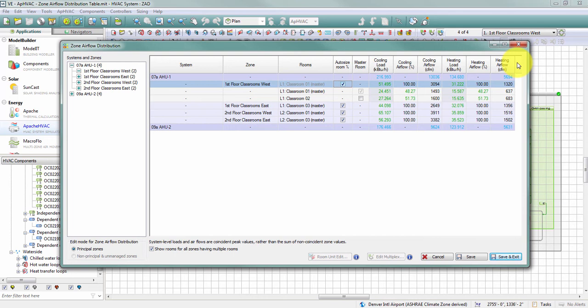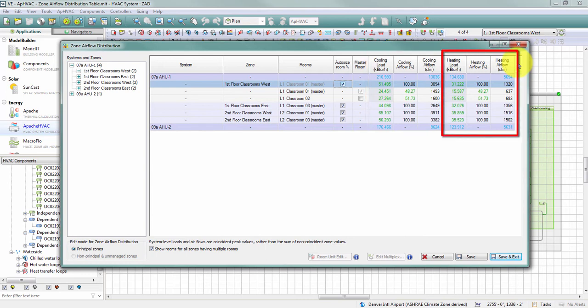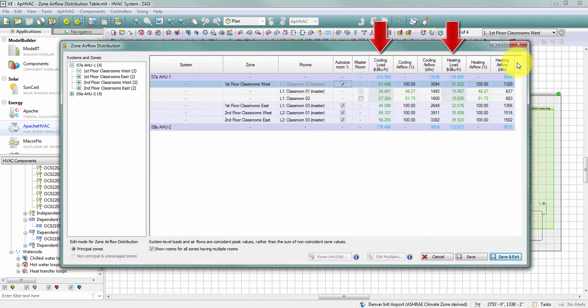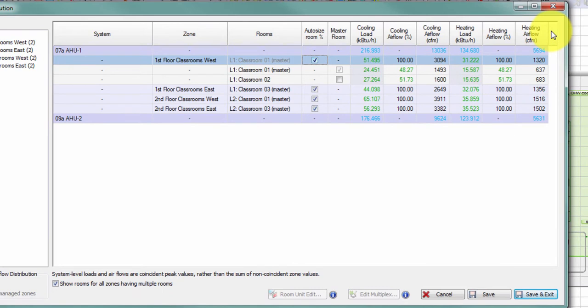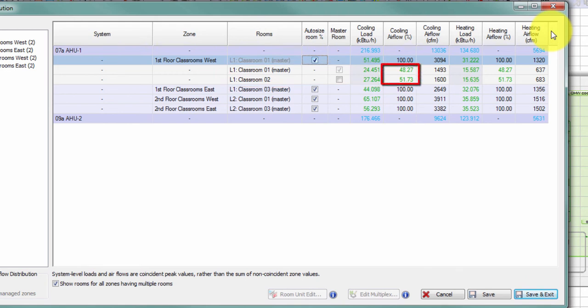The table has columns for cooling load, cooling airflow percentage, and cooling airflow volume, as well as heating load, heating airflow percentage, and heating airflow volume. The cooling airflow percentage represents the portion of total air supplied to the zone distributed to each space. When auto-sized, this is based on the proportional load of the spaces — so in my first floor classrooms west zone, classroom 2 with a slightly larger cooling load receives nearly 52% of the cooling airflow, while classroom 1 receives just over 48%. The cooling airflow volume column shows the actual airflow quantity to the zone and its spaces.